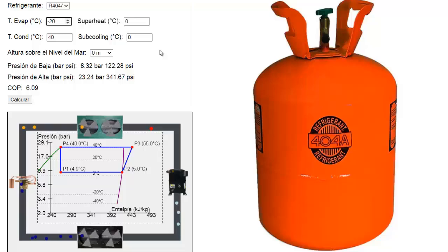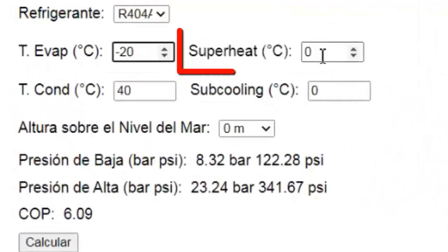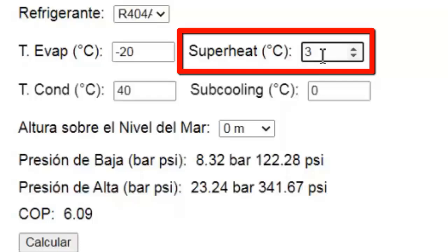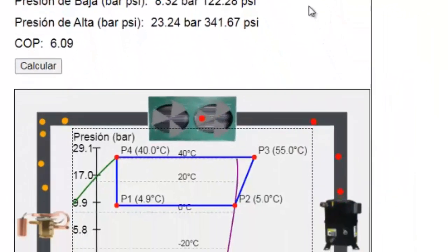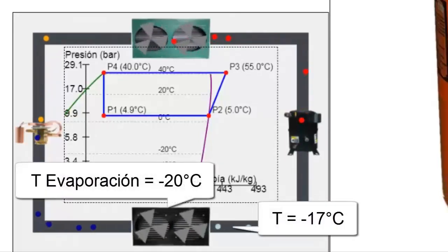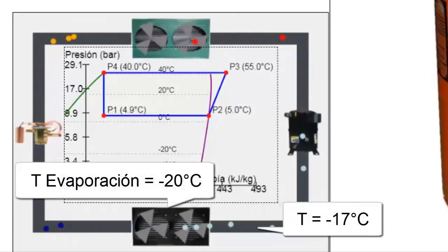For a more precise calculation, we will set the superheat adjustment to 3 degrees Celsius at the evaporator outlet. Remember that superheat is the temperature increase of the refrigerant gas inside the evaporator.